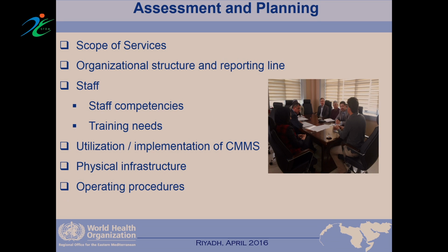In terms of maintenance, you will definitely need what we call a computerized maintenance management system, to ensure that all your data, particularly for repair management, is recorded in one system, so that you are able to monitor and maintain each piece of equipment through its whole life cycle. And definitely you need procedures and systems in place to ensure that whatever you are doing is documented, so that you can develop further and improve your implementation.